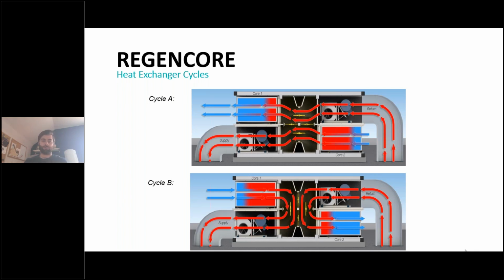So your return air will go through one set of cores, warming it up as you're drawing outside air through an already pre-warmed set of cores, and then depleting that core. And after about 70 to 90 seconds, depending on the unit, that damper switches the paths and changes which core is being heated and which core is being used as reheat.